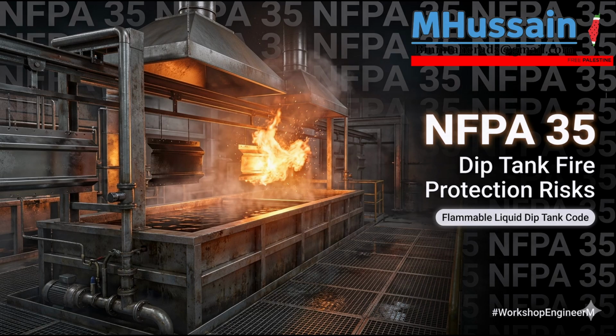Oh, absolutely. If you have an enclosed process area handling Class I liquids, it must be continuously ventilated. The baseline standard is a mechanical exhaust rate of not less than 1 cubic foot per minute per square foot of solid floor area. Correct. But crucially, the standard explicitly mandates where that suction must happen. Yes, it demands that the suction take place at floor level. Not the ceiling. Exactly. Again, we refer back to the physics of vapor density. The hazardous, ignitable vapors are pooling around the ankles of the operators. Right.